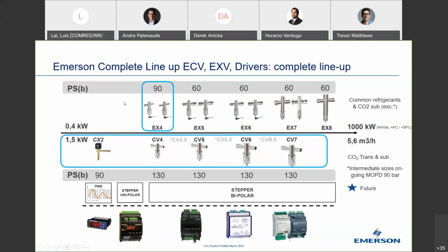We've been selling them, thousands in the last several years. Now that valve has been redesigned to a higher pressure shell. We used to have a valve called the CX. In the last 2 years, it's been redesigned to be called the CV because we've increased the motor torque for CO2. The CV4, the CV5, the CV6 are currently launched. The CV7 is not launched yet.